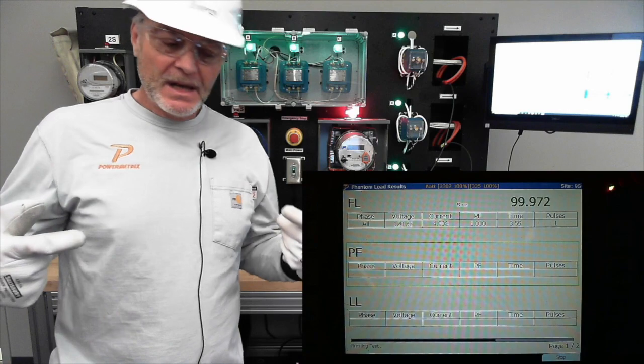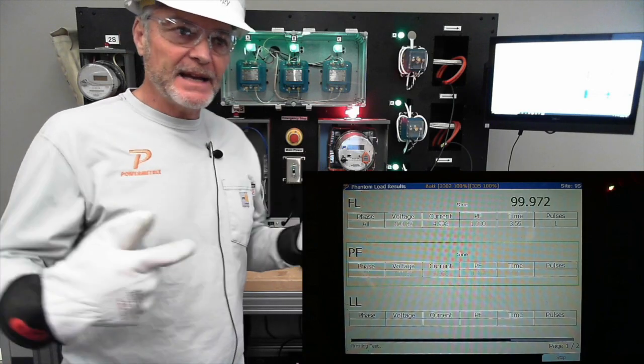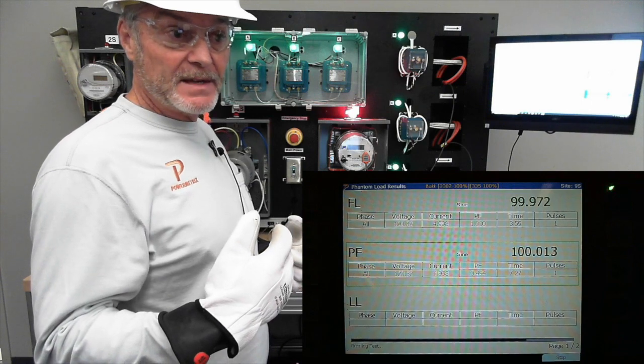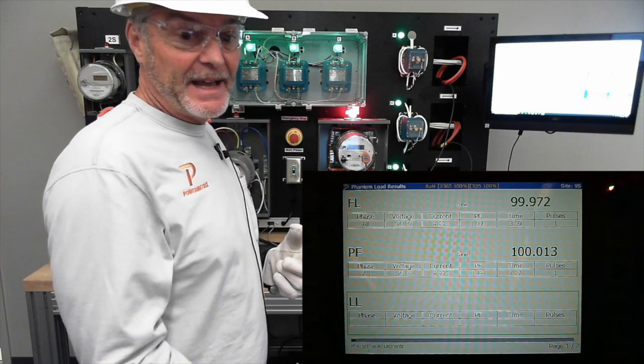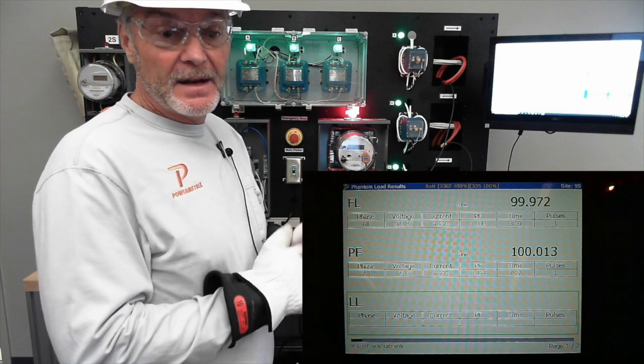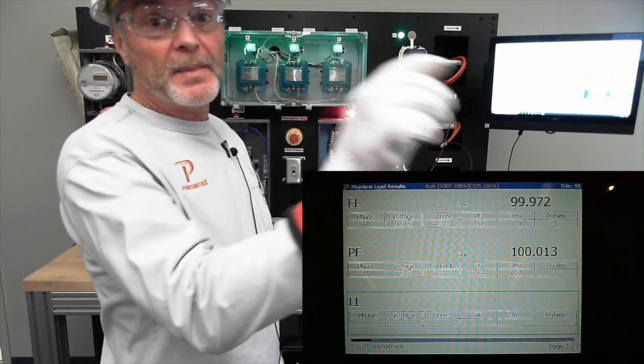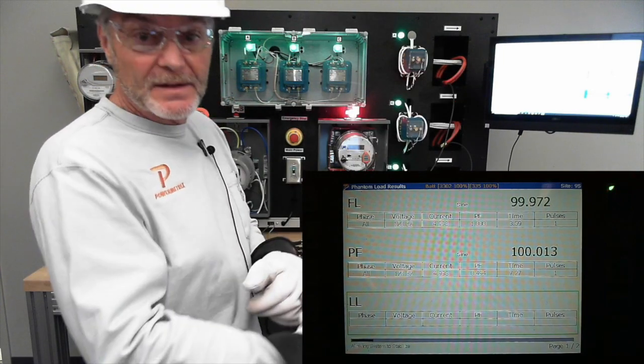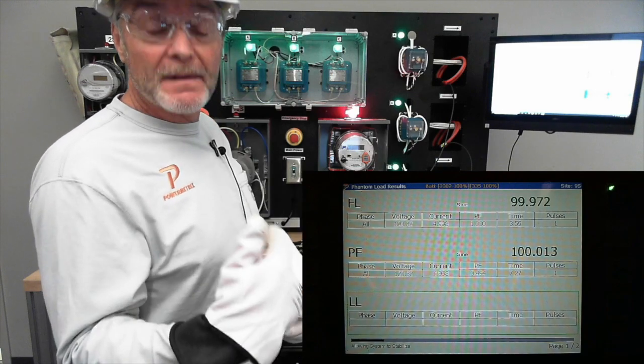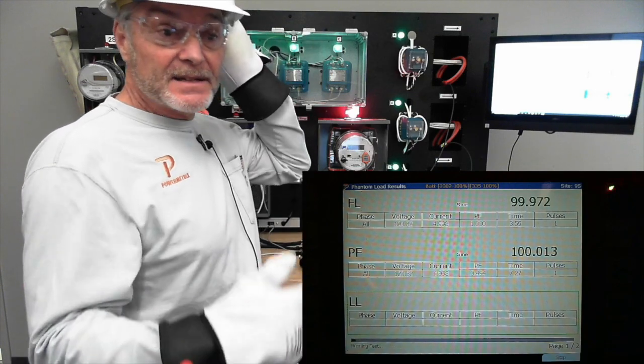So that's another thing you were wondering - why don't you get pulses? We had said, okay, I walk up to a site, I connect up, I'm not getting pulses - this is one of the items on the list. I know it sounds crazy, but if it's not bidirectional and you're receiving power, this thing's not going to do zilch, it's just going to sit there dead. So that could be another one of the reasons why. It could be that you don't have the pickup in the right spot, or you don't have the pickup connected correctly in the back, or it's not in test mode. We'll add this one to the list - it's not bidirectional, and I'm trying to receive power here, so it's going...